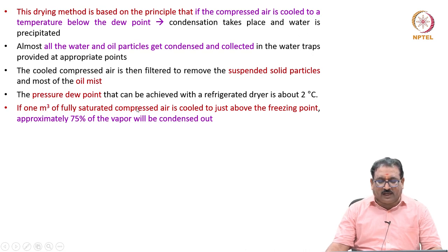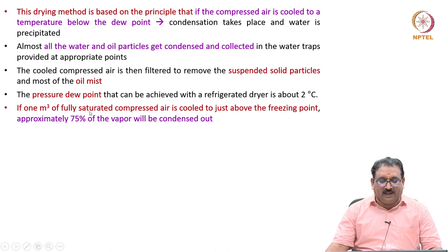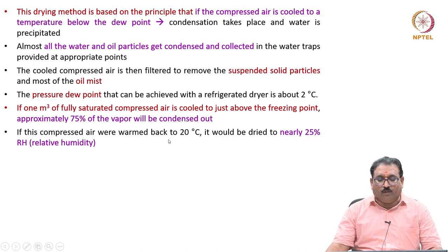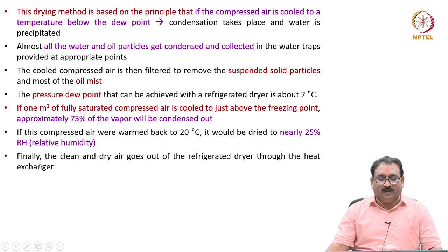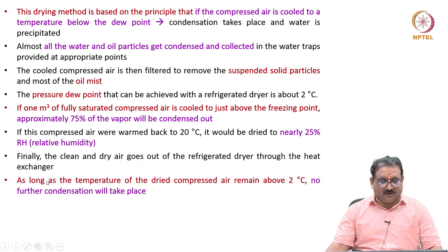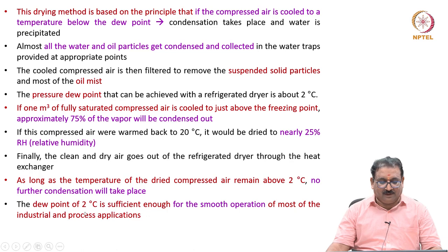If 1 m³ of fully saturated compressed air is cooled to just above the freezing point, approximately 75 percent of the vapor will be condensed out. If this compressed air were warmed back to 20 degrees centigrade, it would be dried to nearly 25 percent relative humidity. Finally, the clean and dry air goes out of the refrigerated dryer through the heat exchanger. As long as the temperature of the compressed air remains above 2 degrees centigrade, no further condensation takes place. The dew point of 2 degrees centigrade is sufficient for smooth operation of most industrial and process applications.